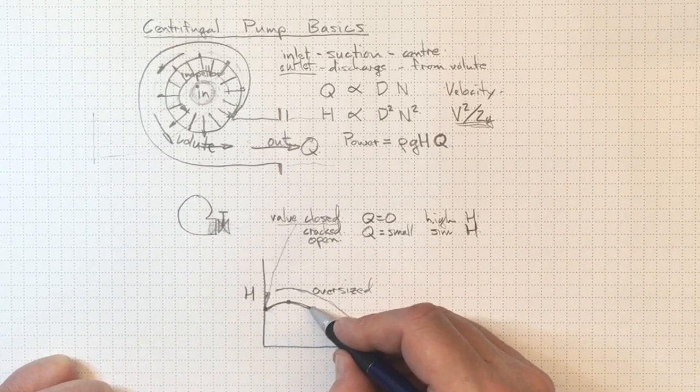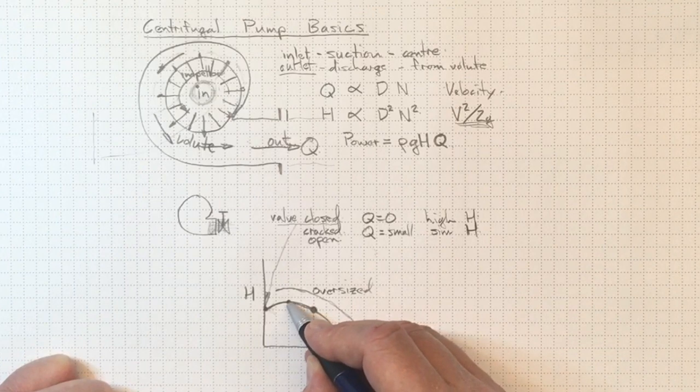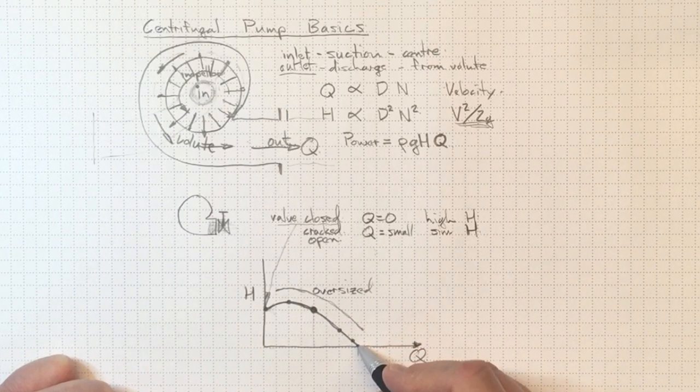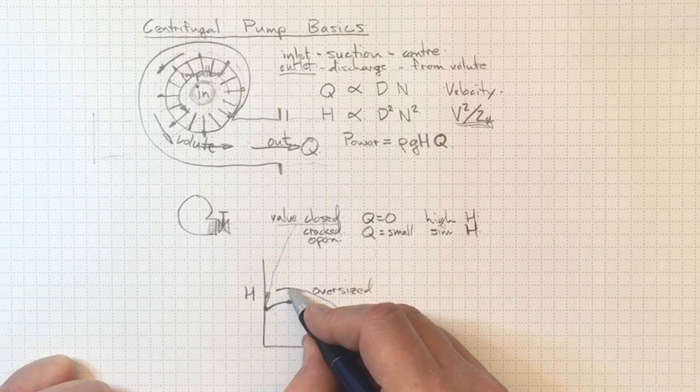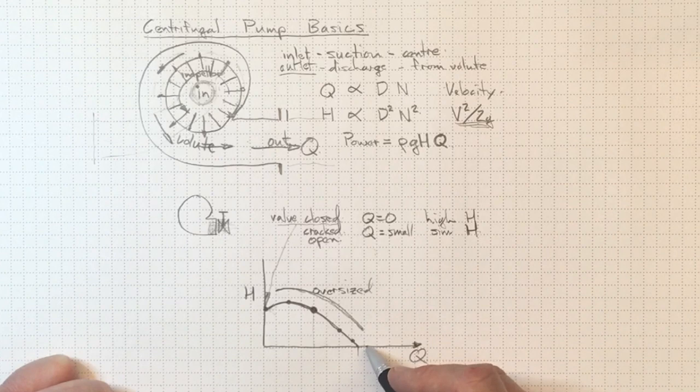It's at a medium level of head and a medium level of flow. And if we go to a lower flow rate, our efficiency may go down. Go to a higher flow rate, our efficiency is going to go down. Go to an oversized impeller, our efficiency is going to go down.